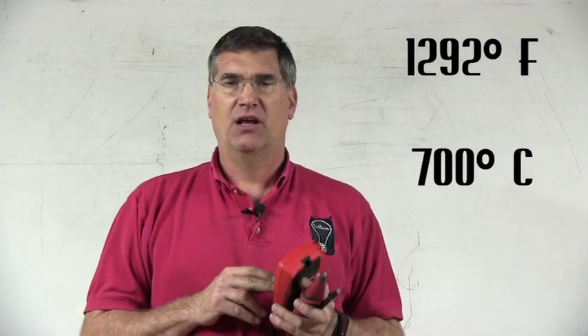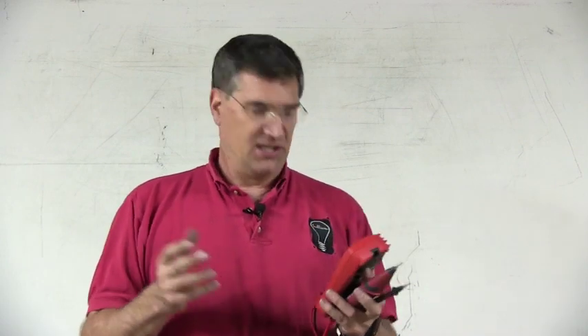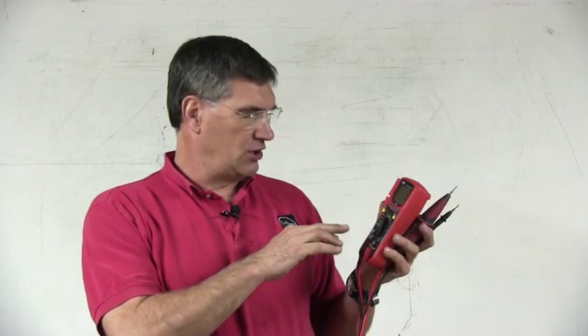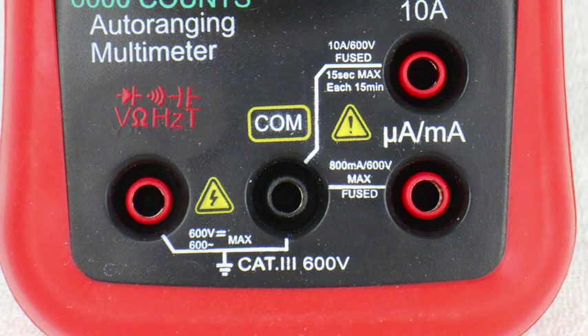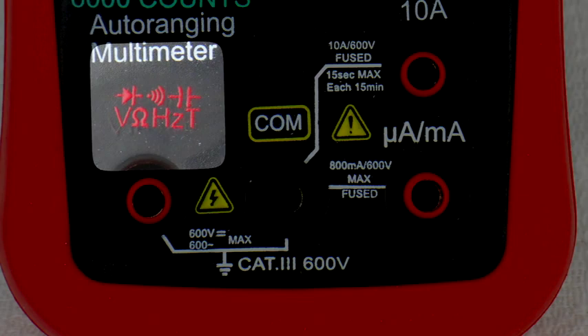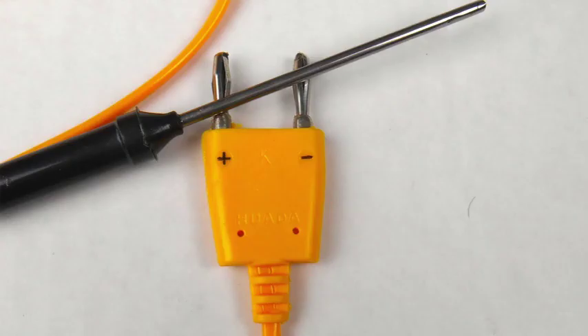The temperature probe is a K-type thermocouple temperature probe that's useful up to about 1300 degrees Fahrenheit, about 700 C. It goes down 40, 50 degrees below zero in both cases, so it gives you a pretty wide range of functionality. It's very simple to use. You simply turn it to temperature, and then you put it into the proper port as indicated on the meter, and there is polarity on the plug.